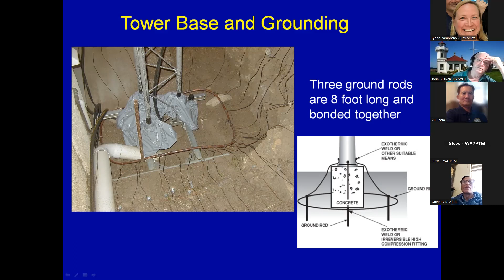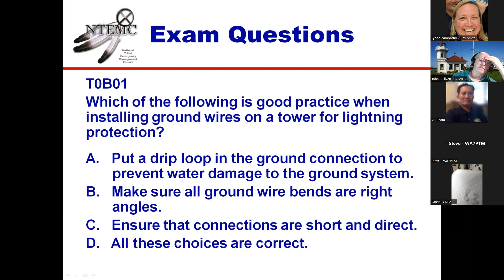All right, so the first 4 questions in this section are kind of a continuation from the last 2 in the previous section, as I mentioned. So, which of the following is a good practice when installing ground wires on a tower for lightning protection? Remember the principles: short, straight, and bonded together. A drip loop in the ground connection has nothing to do with what we're talking about. Make sure all ground wire bends are right angles - that's the opposite of what we want, we want straight. So the only correct answer is: ensure that connections are short and direct.